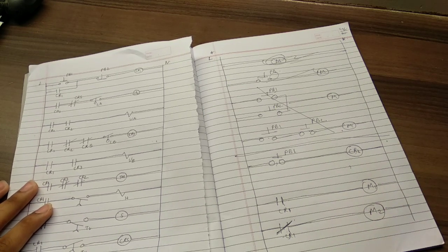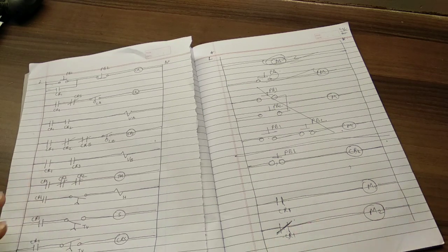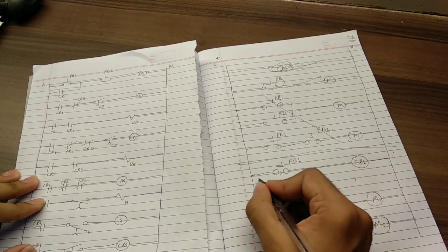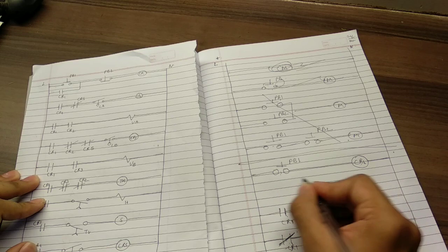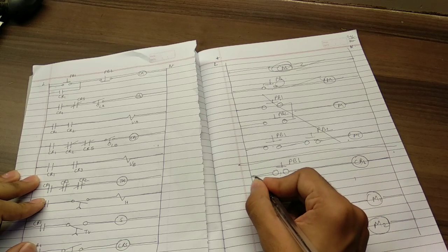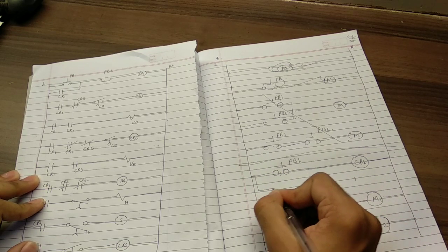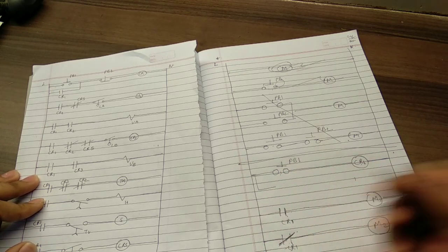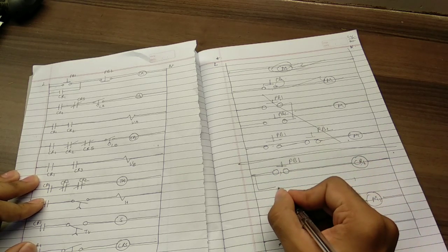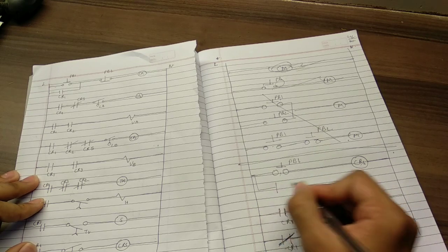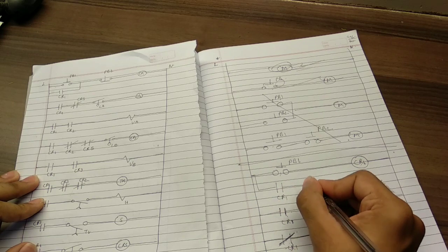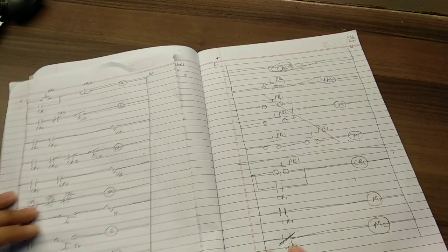So now what if I want to latch this? If I want to latch this, there's a common technique wherein we can add a parallel stage here. So if I'm to add a parallel stage, I can add it like this, or I can drag it from here too. It's just a normal circuit diagram, you can say. And I will have a control relay CR1 over here. So effectively I've created a latch.